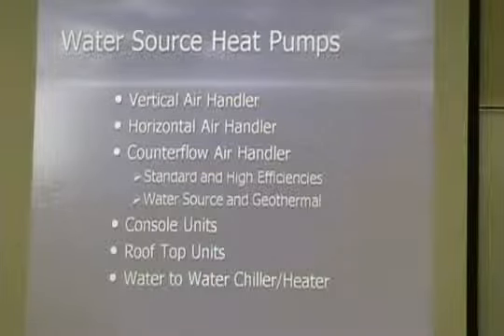Another thing you can do with the water source heat pumps is the water chiller heater. We have one in our building. It's a reverse cycle chiller, meaning that we can make 45-degree water, or we can make 120 or 130 degree hot water. In our building, we have a variable volume air handling unit with a water coil in it. In the wintertime, we make hot water with our chiller.